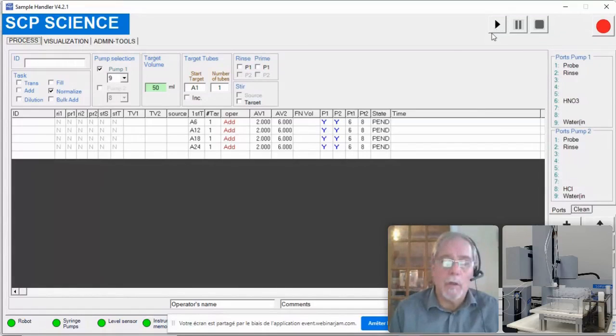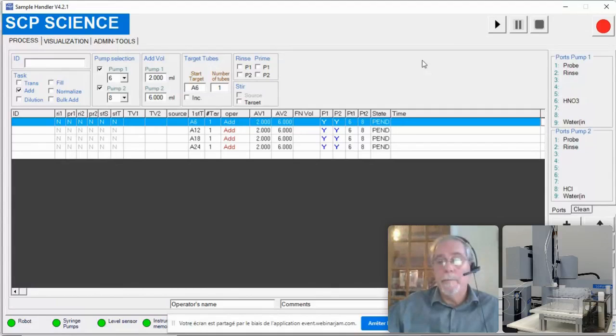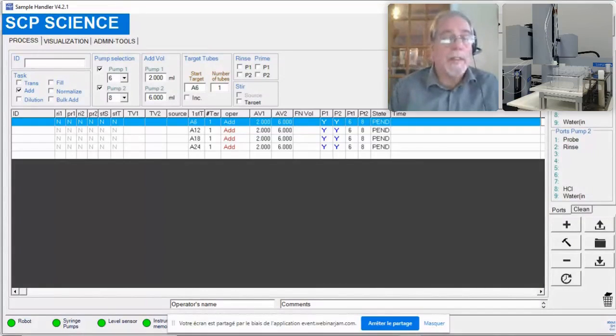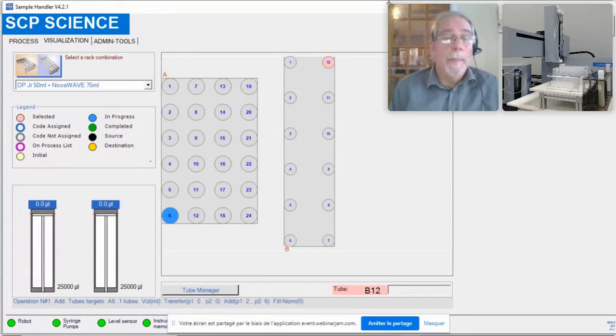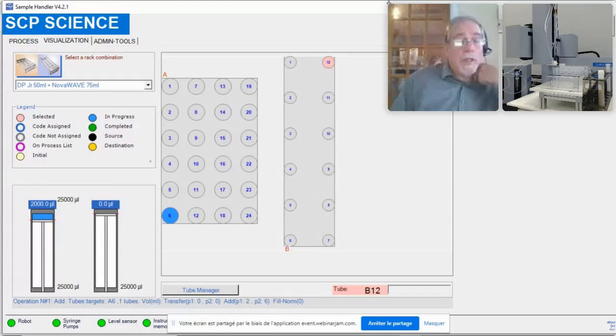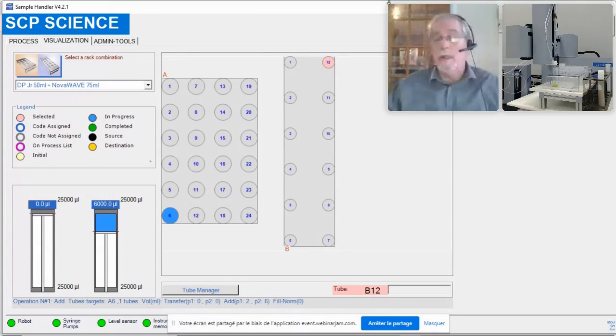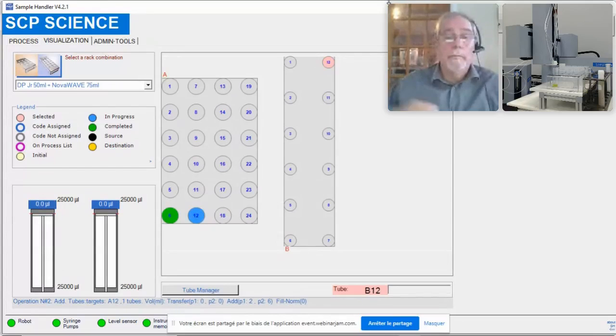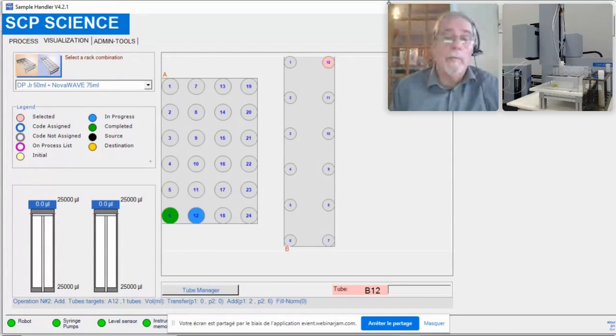So we're not mixing the nitric acid and the hydrochloric in a bottle, then dispensing. We're going to dispense the nitric acid out of one pump and the hydrochloric acid out of the other. So 2 of nitric and 6 of HCl. So John will press the start button and away we go. On the visualization tab, you can see which vessels are going to have the liquid added to it. So the first step that it's doing is that it picks up the aliquots of the reagents that it's going to dispense. Then it will dispense it in the tubes. So you can see that it has dispensed the blue, the nitric, and then the HCl into the tubes.